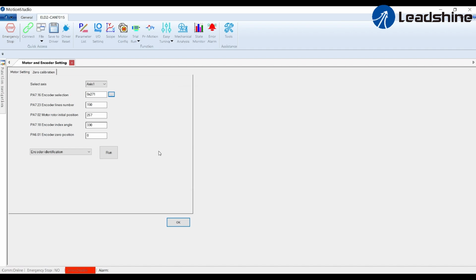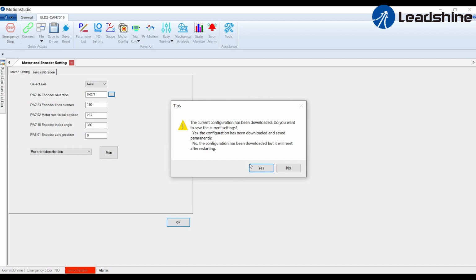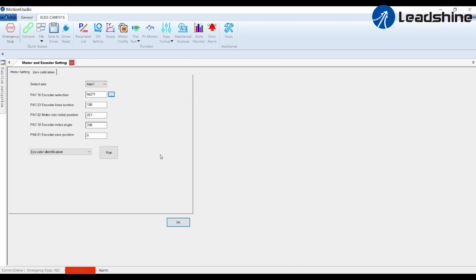If the driver is alarming, please click OK and Yes. After saving parameters, restart the power supply to clear the alarm. If any alarm cannot be cleared, please check the encoder or Hall signal connection and encoder setting in zero calibration.